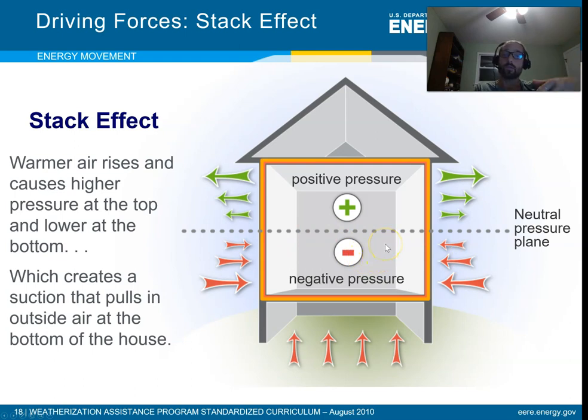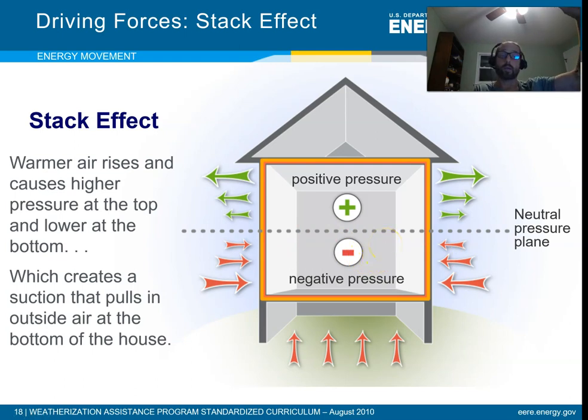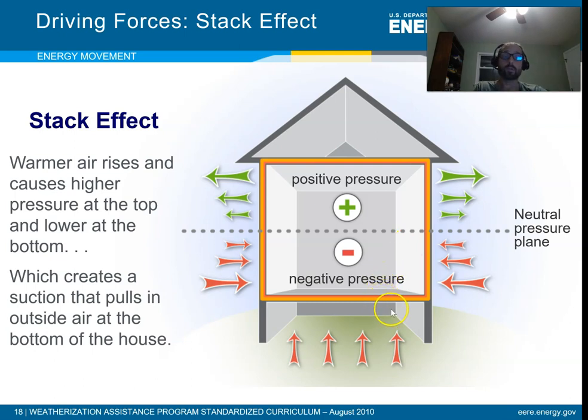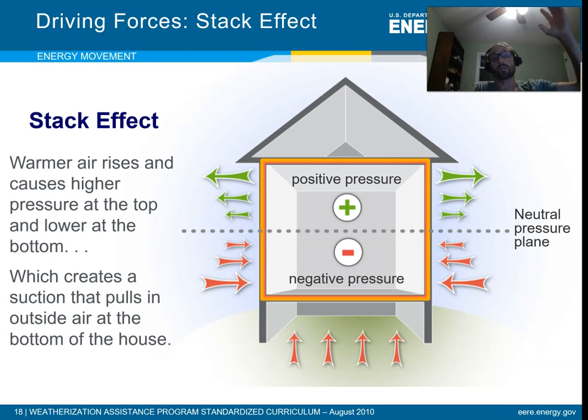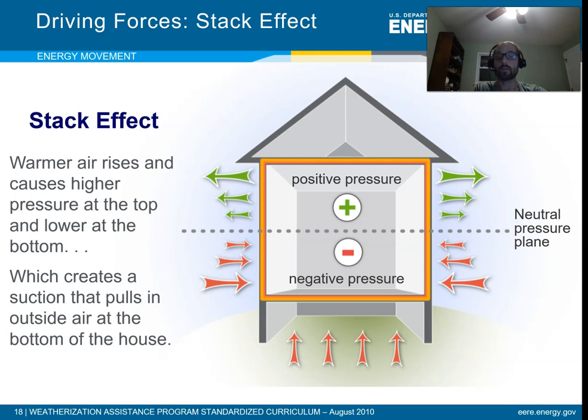The further you get away from the neutral pressure plane, the bigger the magnitude of that delta P. The higher above it you go, the higher the pressure; the lower below it you go, the more negative the pressure becomes. That's just the nature of the physics.